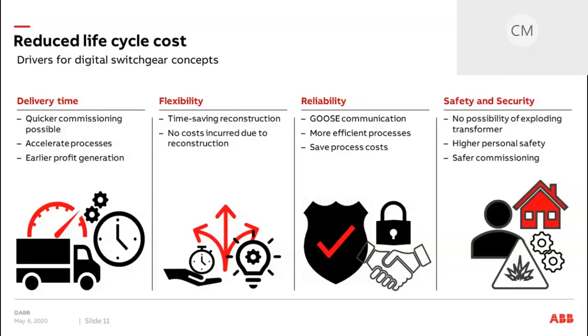The third reason is reliability. Digital switchgear is based on well-known established switchgear hardware platforms and uses sensors. With these sensors, less human interaction is required, which leads to decreased risk of malfunction. They are smaller and reduce the risk of isolation degradation in the switchgear compared to conventional transformers. Furthermore, they are immune against grid disturbances, especially the voltage transformers and ferroresonance phenomena.